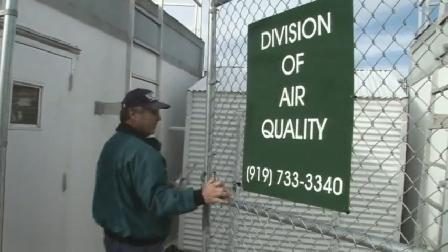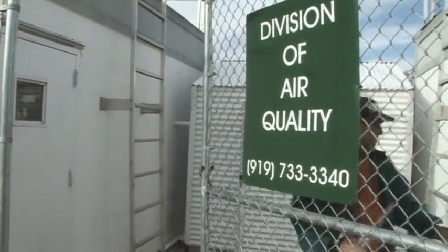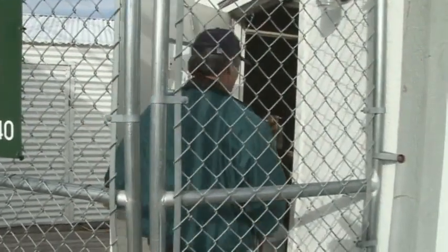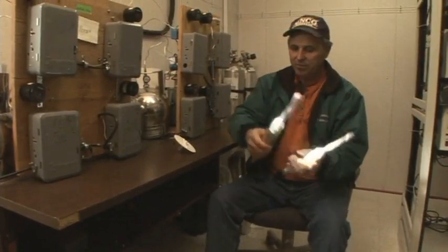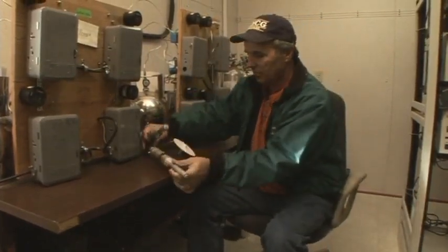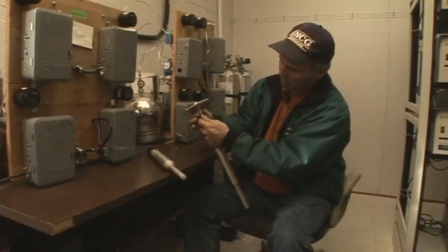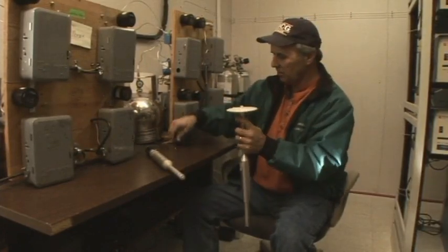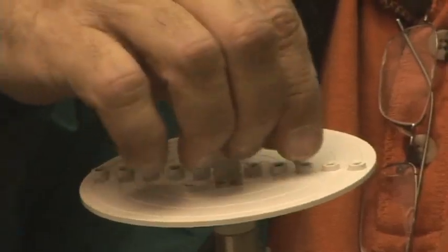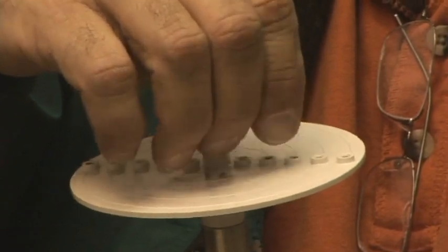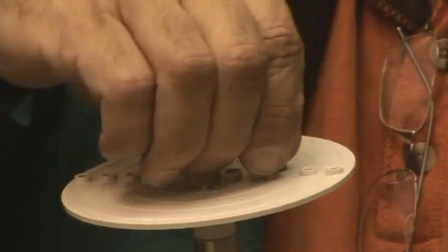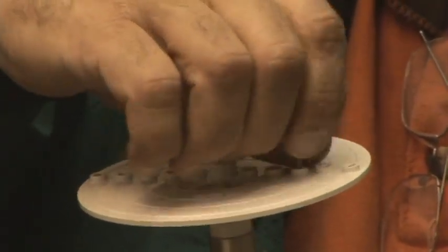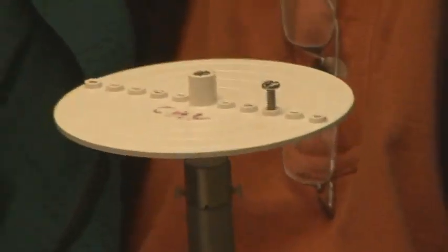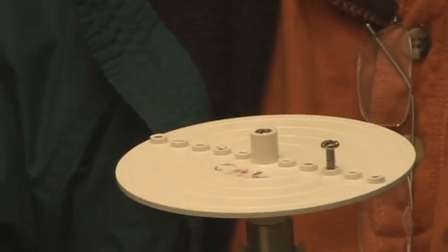The torque test is performed by removing the sensor from the tower and bringing it into the shelter. On a flat surface, place the sensor on its side so that it is laying flat on the bench. Attach the torque wheel to the shaft of the sensor. A grommet or small piece of tubing can be used to make a snug fit. Now that the torque wheel is attached, place one of the screws into the middle hole on one side of the wheel. With a 1 gram screw in the third hole, gravity generates 3 gram-centimeters of force of torque.